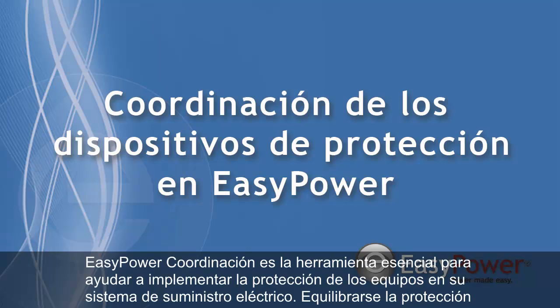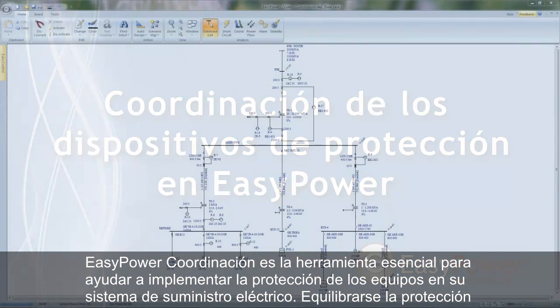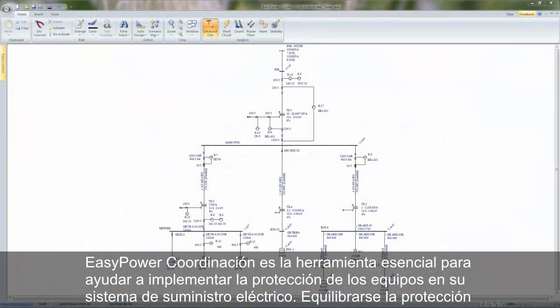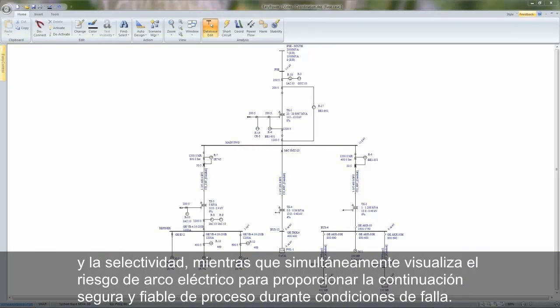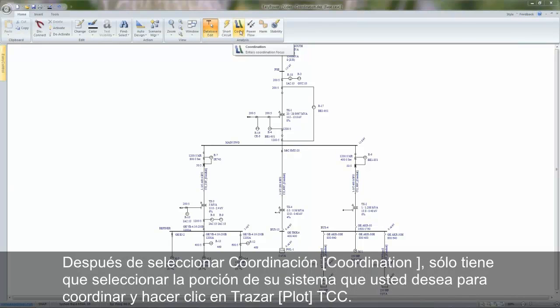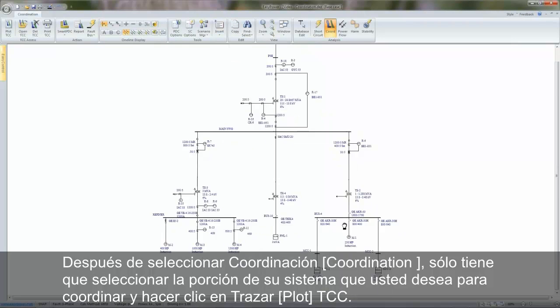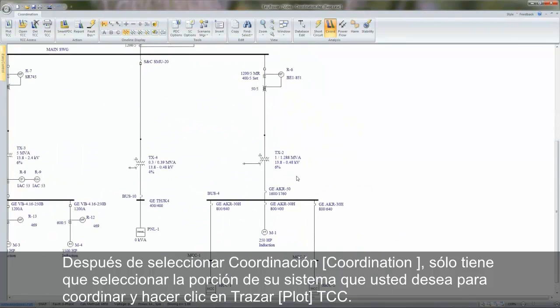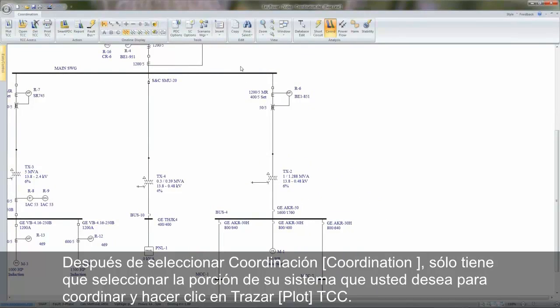EasyPower coordination is the essential tool to help implement protection of equipment in your electrical supply system. Balance protection and selectivity while simultaneously visualizing arc flash hazard to provide safe and reliable continuation of process during fault conditions. After entering the coordination, simply select the portion of the system that you desire to coordinate and press the Plot TCC button.